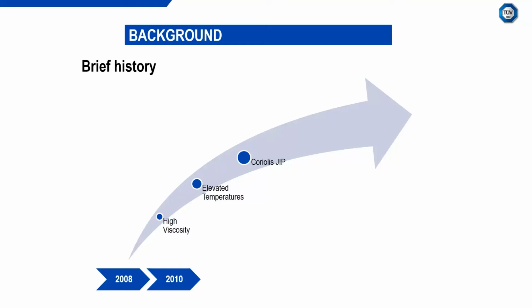So we formulated a JIP. We managed to get several sponsors for this large project, which was great. I think we had in the end between about 10 or a dozen sponsors, which was fantastic. Looking at the main Coriolis manufacturers, we had the three main manufacturers, and that was Endress+Hauser, Emerson Micro Motion, and Krohne. And we tested a variety of their commercially available Coriolis meters in a couple of different sizes, 3-inch and 4-inch in particular.